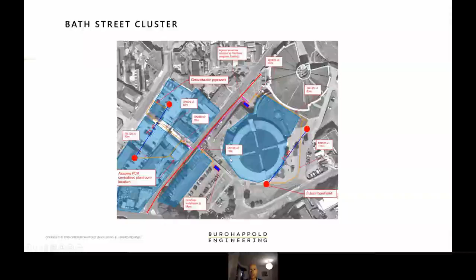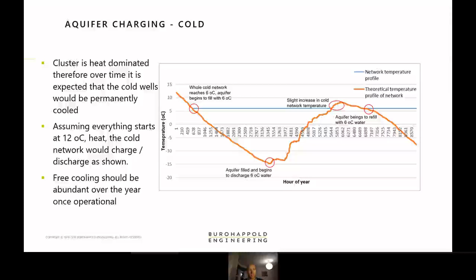The principle is that we will have a heat-dominated cluster. So what you're looking for with the 5th generation is heat balance. In this first cluster, we've got heat domination, which means we have to depend upon the regeneration of the wells, so our cold well will tend towards a 6 to 12 degree temperature. But in the future, as we add more commercial onto the scheme, we'll get a greater balance between cooling and heating. The advantage of this is we're able to deliver free cooling directly into most of the uses.